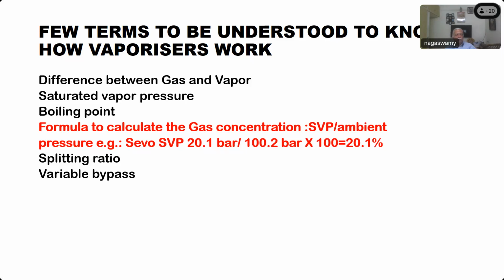And what do you mean by variable bypass? That is the amount of gas that can go without entering the chamber. That can be adjusted. It is not a fixed amount. You can adjust it by keeping the dial setting at various levels. So it's called variable bypass.